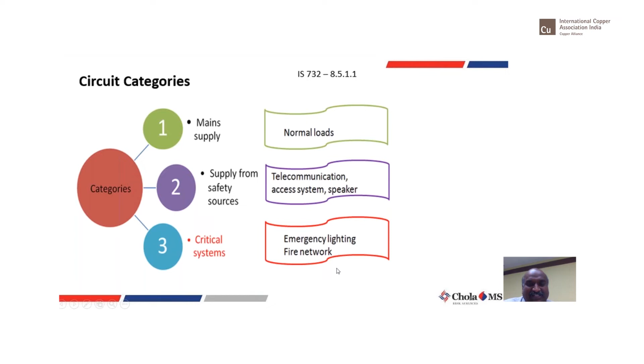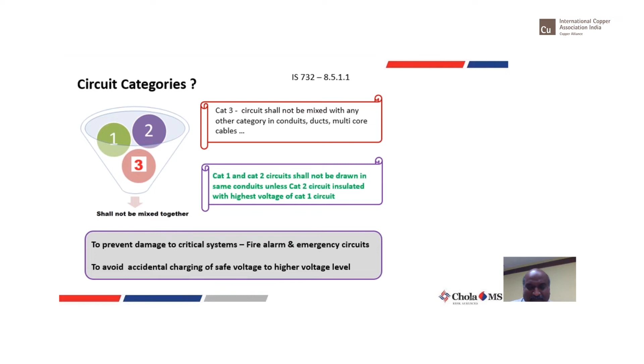Under category 1 and 2 as well, as far as possible please maintain them separately. If laid in one conduit or adjacent to each other, for instance with signal cables, data cables and telecom, it can cause interference and create noise in the circuit, and also cause heating. Special circuits might have shielding and proper protection, so they can be laid nearby, but for better output it's always best to segregate category 1, 2, and 3 circuits. This prevents damage to critical systems like fire alarms and avoids accidental charging of safe voltages.